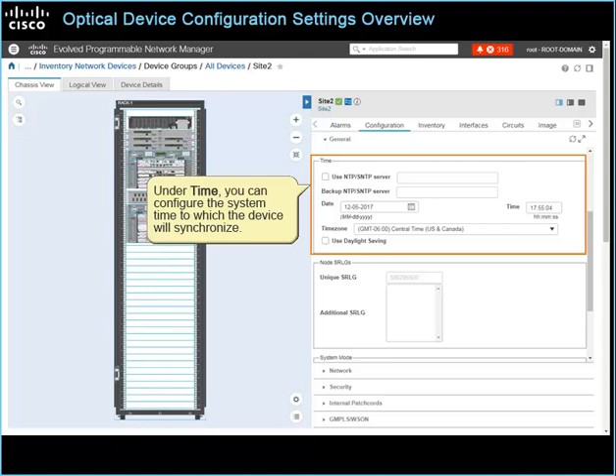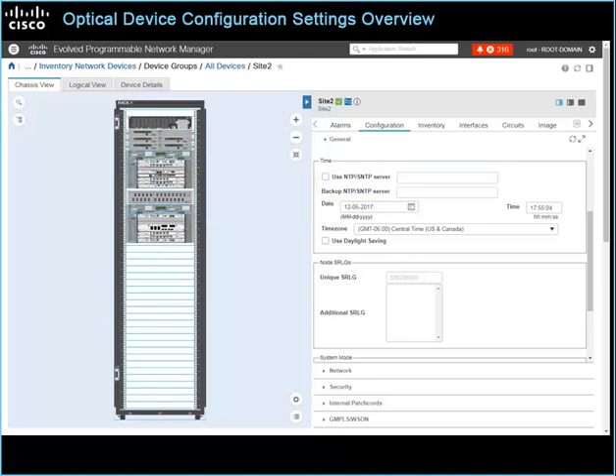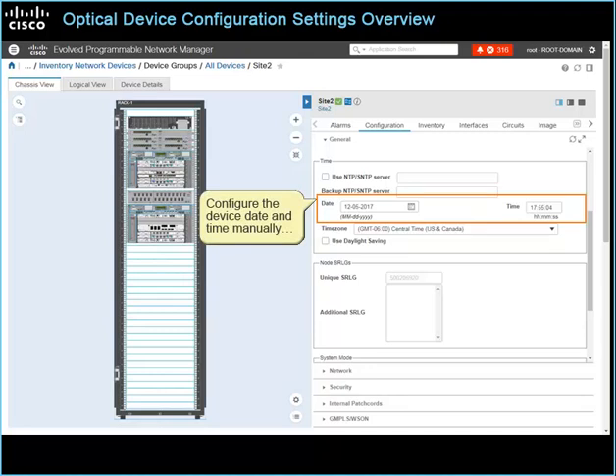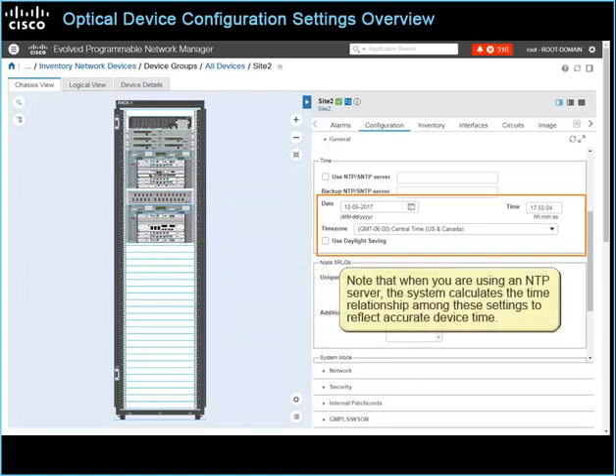Under Time, you can configure the system time to which the device will synchronize. You can use a network time protocol, or NTP server, and also assign a backup server in case of a primary server failure. You also can configure the device date and time manually, and indicate the device time zone and whether to apply daylight saving time. Note that when you are using an NTP server, the system calculates the time relationship among these settings to reflect accurate device time.